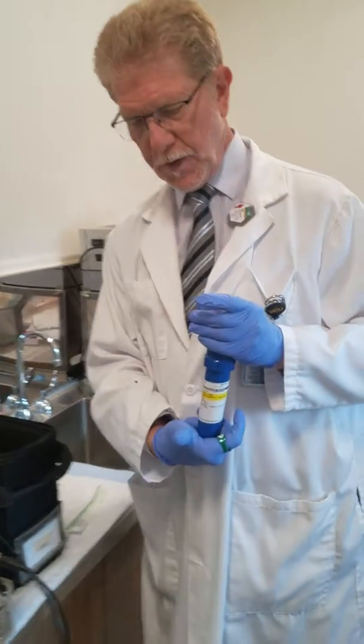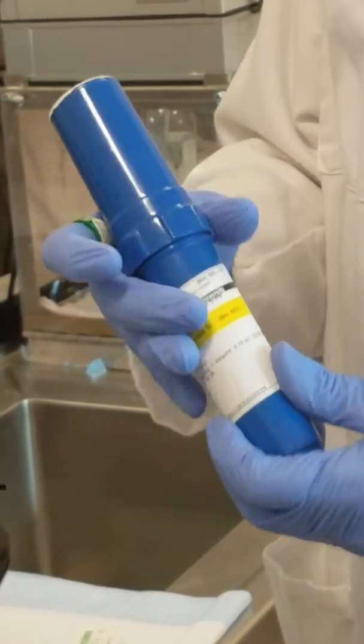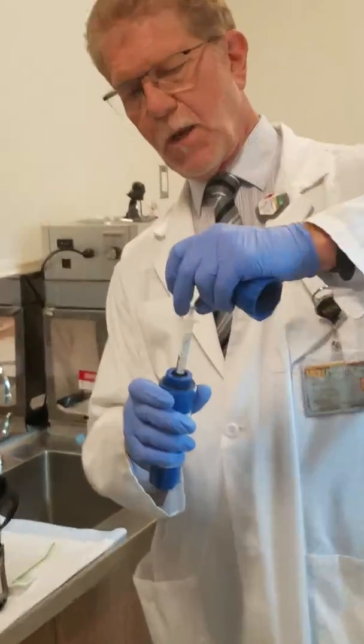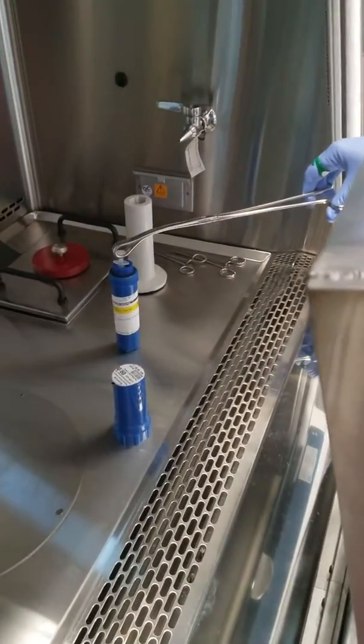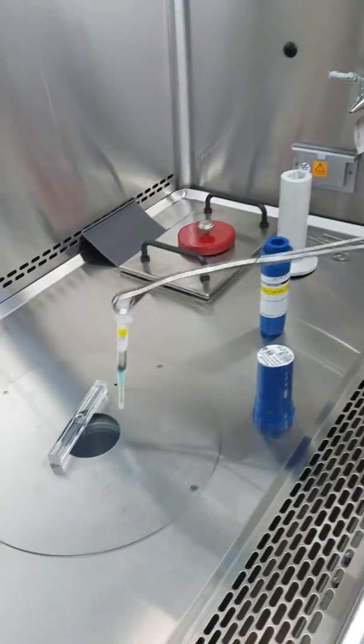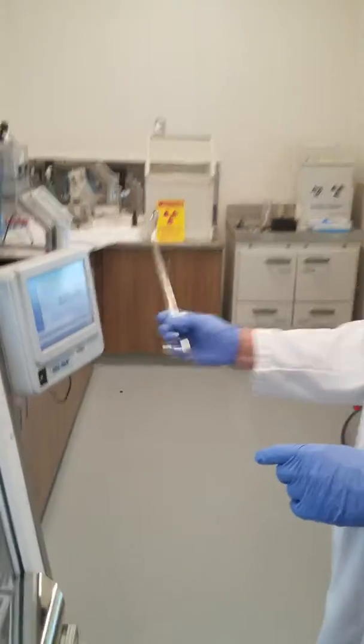The next thing we do is pop out our syringe — this little unit dose right here. It's labeled with the appropriate information and it's lead covered. Here is the syringe that's actually inside, and it's labeled again one more time. We come over to our hood and drop this into our dose calibrator to be read. You will note that we have 364 microcuries of activity being given off. Then we log that in, remove it, and get ready to inject into a patient when the patient arrives.